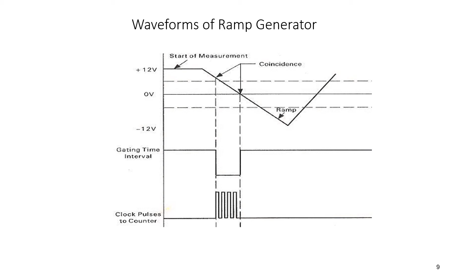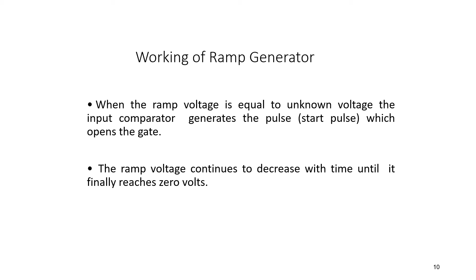Once the input voltage and the ramp are at the same level, then the gate is open and the clock pulses are counted by the counter. Here, when the ramp voltage is equal to the unknown voltage, the input comparator generates the start pulse, which opens the gate. Next, the ramp voltage continues to decrease with time until it finally reaches 0 volts. When the ramp voltage reaches 0 volts, the ground comparator generates an output pulse, the stop pulse, which closes the gate.